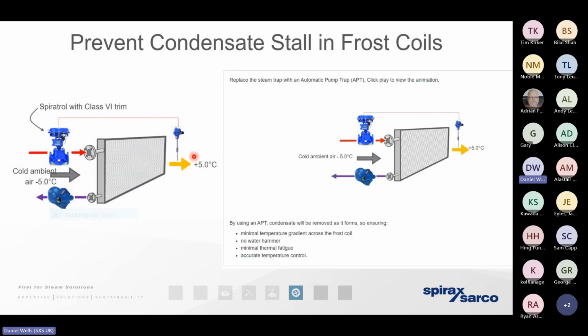And we also know that we may potentially come across issues in control valves if we've got a high pressure downstream of the trap. That back pressure may mean that there's insufficient pressure within the body of the frost coil itself in order to pressurize the condensate and move it across a trap. In many cases, it's going to be beneficial if we remove the trap altogether and move towards what we call an APT, an automatic pump trap. As we've mentioned in previous presentations, an automatic pump trap can remove the condensate regardless of the pressure conditions by simply borrowing a little bit of upstream motive energy from the steam in order to help drain that condensate away.